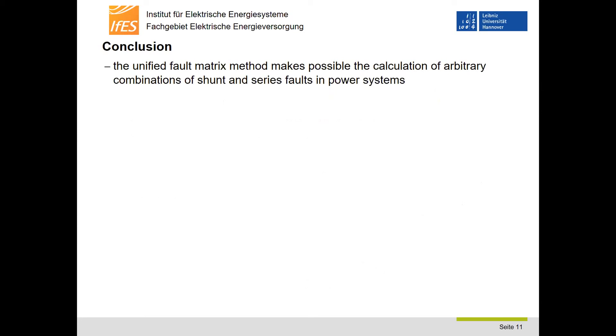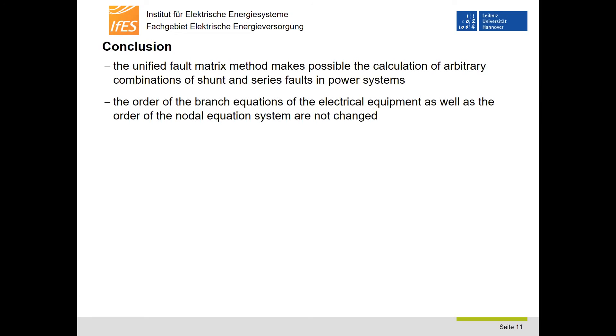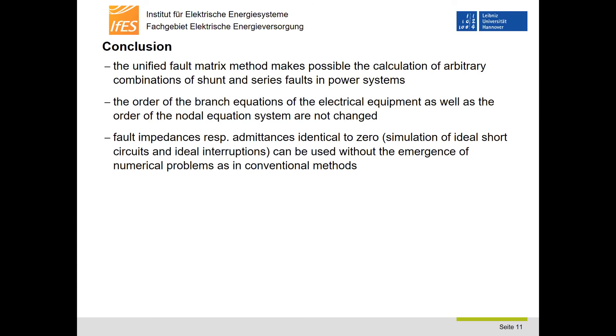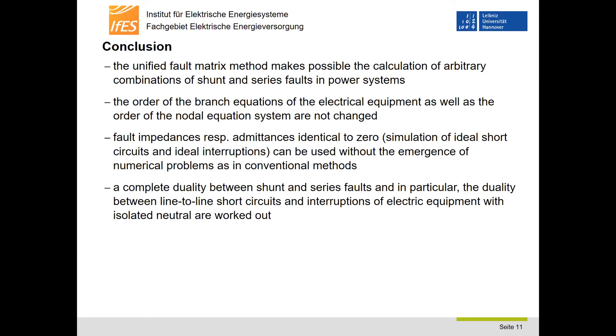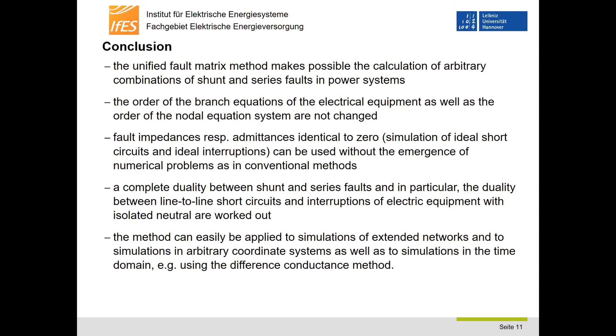To conclude, the unified fault matrix method makes possible the calculation of arbitrary combinations of shunt and series faults in power systems. The order of the branch equations of electrical equipment as well as the order of the nodal equation system are not changed. Fault impedances or fault admittances identical to zero, representing ideal short circuits or ideal interruptions, can be used without numerical problems. A complete duality between shunt and series faults — in particular the duality between line-to-line short circuits and interruptions of equipment with isolated neutral — is worked out. The method can easily be applied to extended networks, arbitrary coordinate systems, and time domain simulations, for example using the difference conductance method.